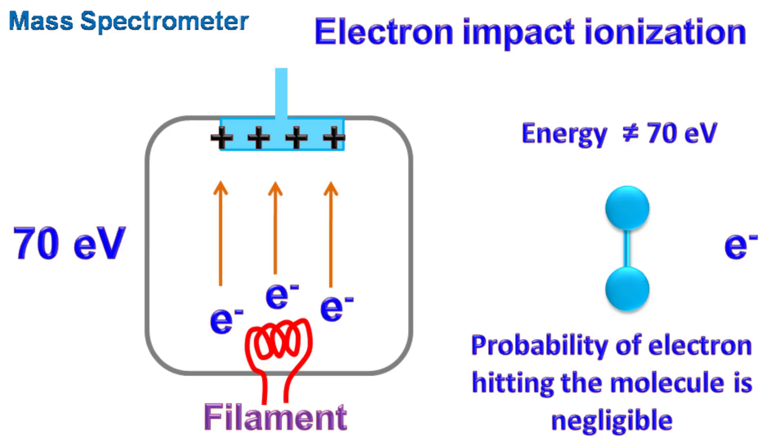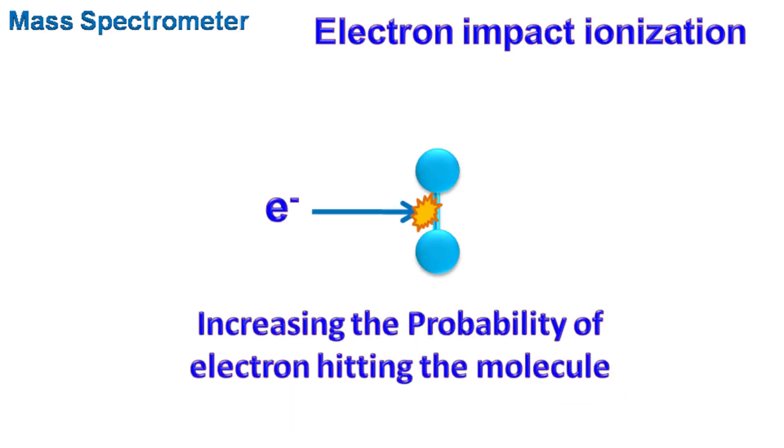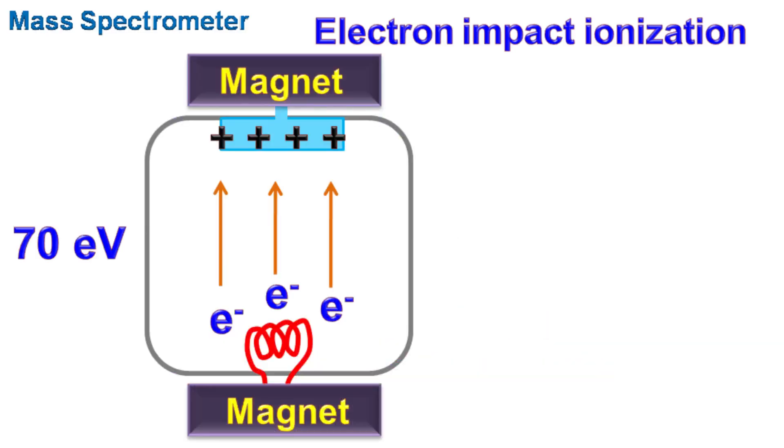Besides keeping energy of electrons to 70 electron volts, to further increase the probability of electrons hitting the molecule, a weak magnetic field is applied parallel to the direction in which the electrons are traveling. This magnetic field makes the electrons move in a helical path. Hence electrons spend more time in the chamber and the probability of electron hitting the molecule increases.